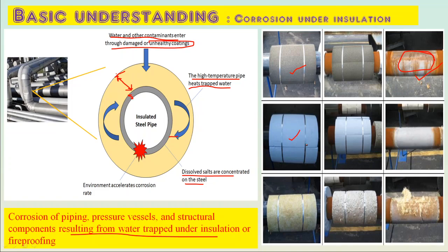But this silicate block, you haven't seen any moisture ingress over a period of time, and this insulation system seems to be good. It's our normal conventional insulation system, rock wool, and here you can see the damage and moisture ingress which led to the formation of iron scales. So we will see this in detail.